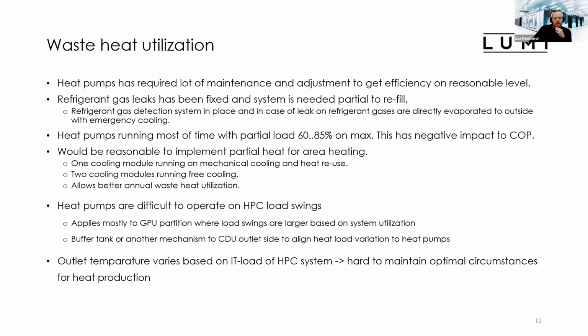Okay, so quickly, we have done some refill of the refrigerant gas and fixed those leaks to get the system running as designed. It would be reasonable to implement partial free cooling for the area only when there is no demand on the district heating network, so we could utilize the waste heat only for the area, running a single cooling module on mechanical cooling and the other on free cooling.